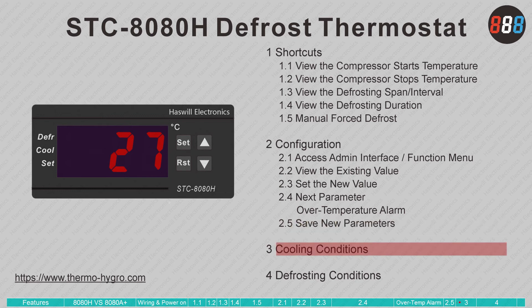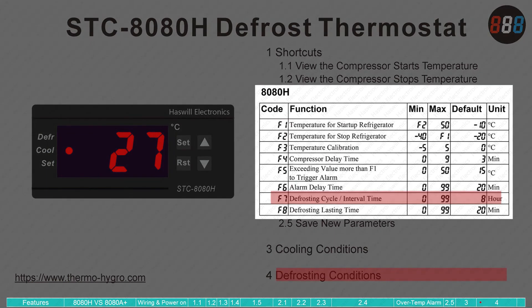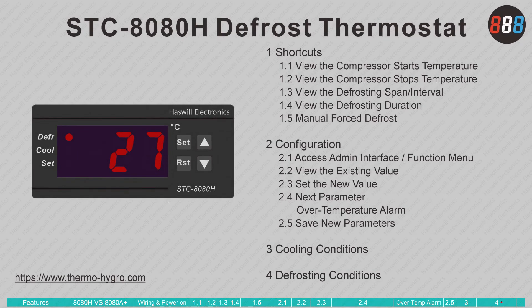If the room temperature is higher than F1, the cool light will flash, indicating the compressor delay time before it starts. After the hours set in F7, the compressor stops and defrosting begins — the defrosting indicator light turns on — and this process continues for F8 minutes. That is all about how to use and set the STC-8080 temperature controller.